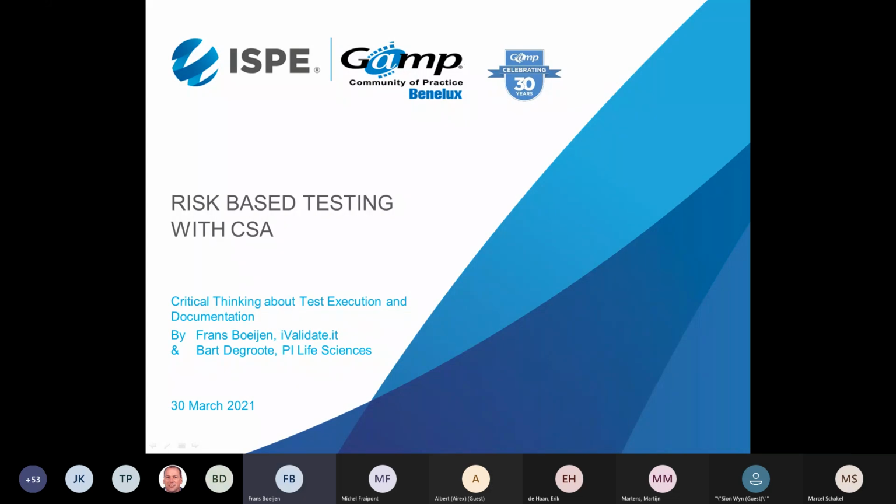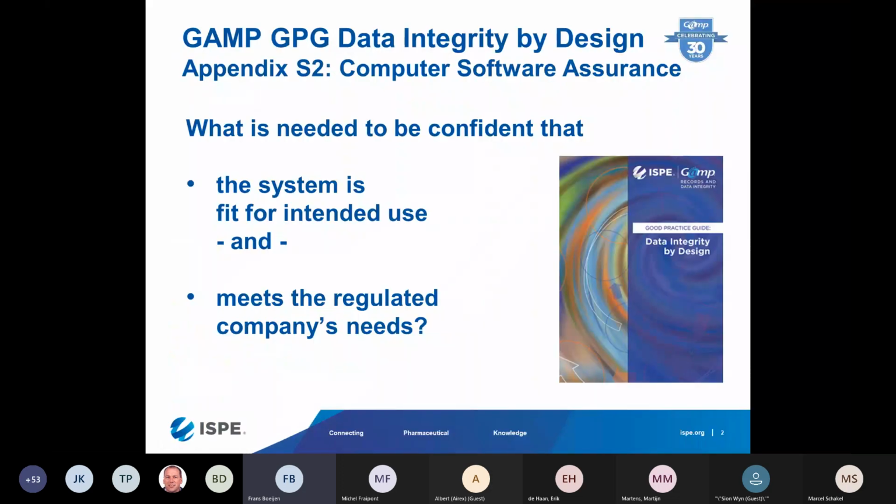Yes, good afternoon. I hope the screen is visible and you can hear me, Marcel. Yes, we can. Okay. Welcome. Thank you, Sean, for the perfect introduction to the second presentation, where we continue. Both Bart and I have a joint presentation about risk-based testing based on CSA. We go into more detail on Appendix S2 of the Good Practice Guide on Data Integrity by Design, because we have to answer a very important question: what is needed to be confident that the system is indeed fit for intended use and meets the regulated company's needs. So it's, as Sean mentioned, not the need of the inspector, but what your company needs to prove that the system is fit for intended use.